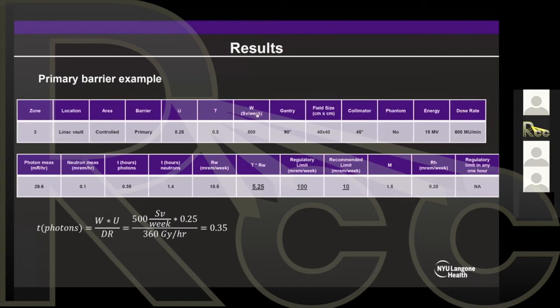What is your workload? Here, this is just an example. I put 500. I think NCRP 151 recommends 450 is going to be the most common one, but we're going to use 500 for this. Where was my gantry? Obviously, it was at 90, so I can have the beam incident to that primary barrier. Field size, as I said, maximum opening with the collimator at 45, so I can maximize the primary beam in the corners. Do I have a phantom in the beam? No. Energy, highest. Dose rate, highest, right?